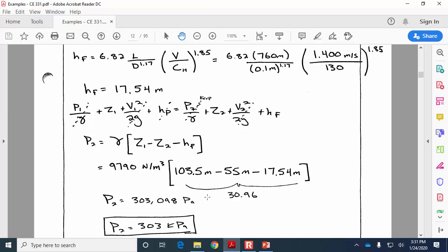So what we're talking about, 1.5. Okay, so we're talking 1 kilopascal out of 300 is the difference if you keep the velocity head versus take it out. So I think you're probably getting a sense for why often we just ignore the effect of velocity head: unless the water's really moving fast, there's just not that much energy tied up in the velocity head. But if you left it in, good for you. That's even more accurate.